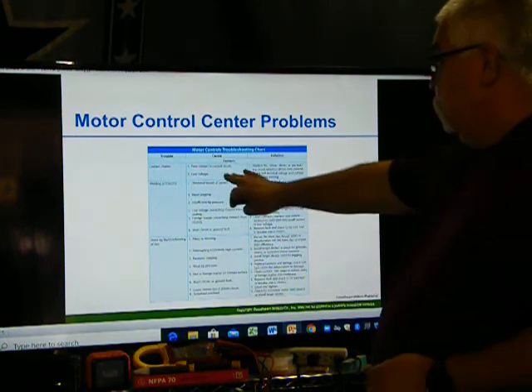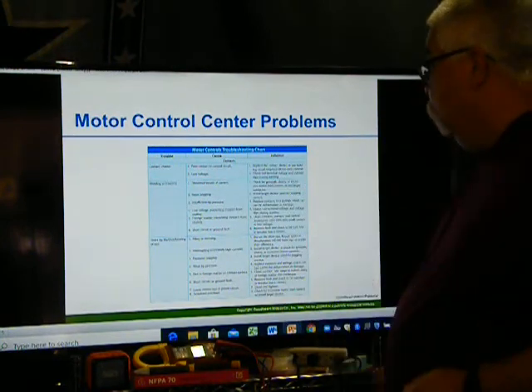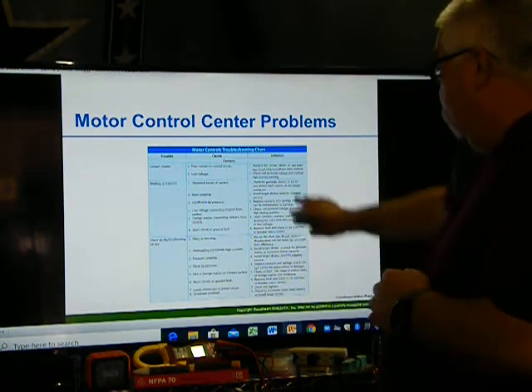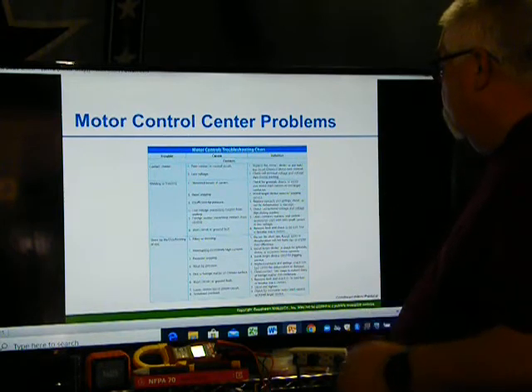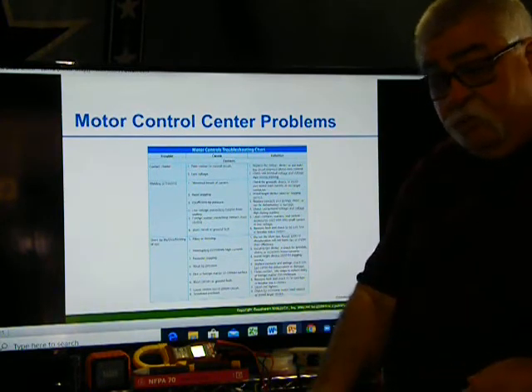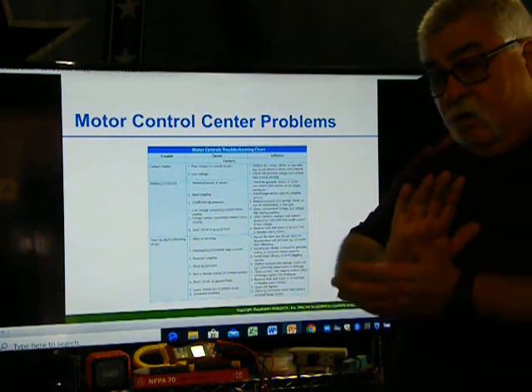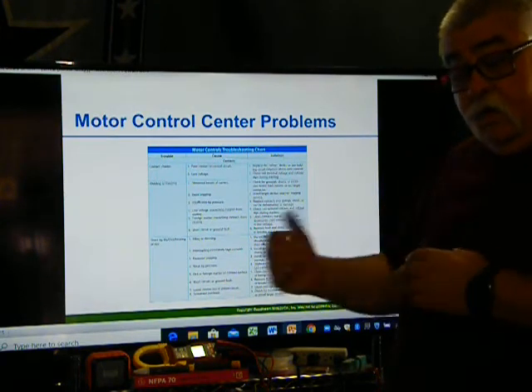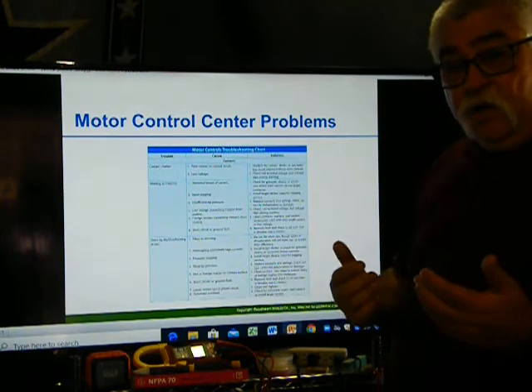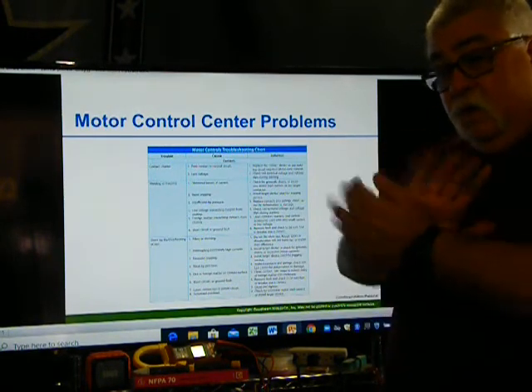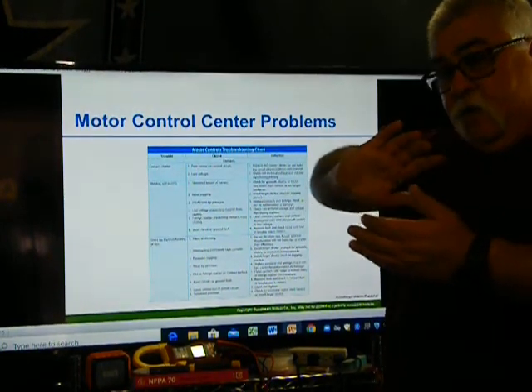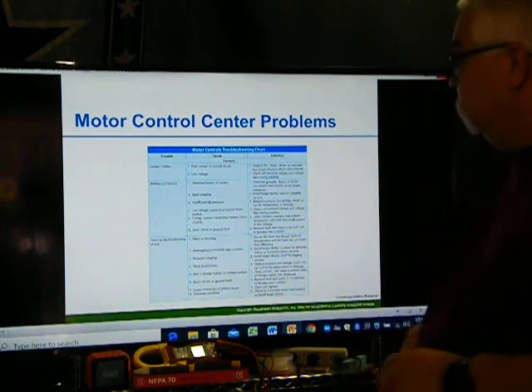All right, so the contact chattering. The contact, I'm talking about that. That'll make poor contact control. Replace the contact, check the coil terminal voltage. Make sure your voltage is good enough on your coil. If your transformer is at 7.5%, guess what the voltage is on these contacts. If your voltage is too low, they won't close. It's not enough to maintain it closed.